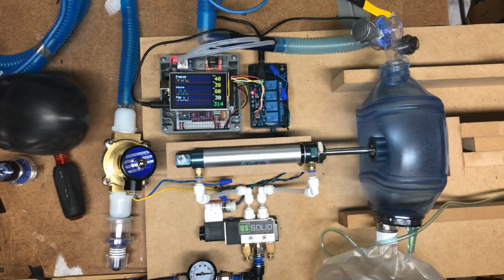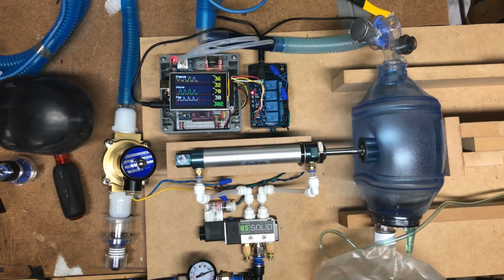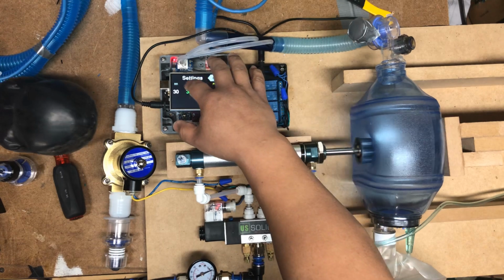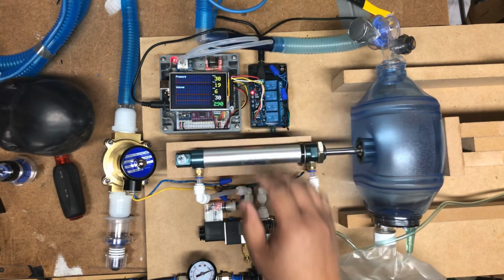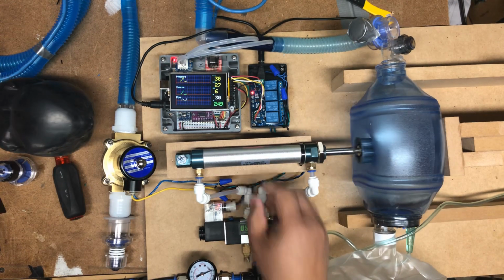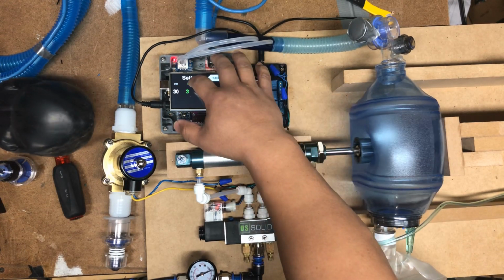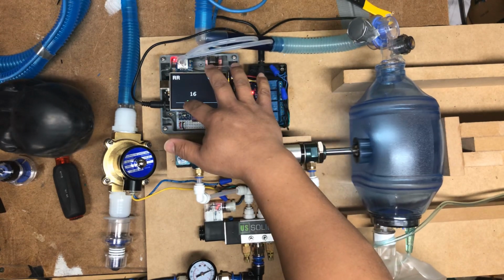Now let's look at pressure control mode. For pressure control mode, I'm going to back down on the air regulator. I'm going to set the tidal volume very high, or whatever volume we want. To better see this, I'm going to set the respiratory rate low. Say 14.